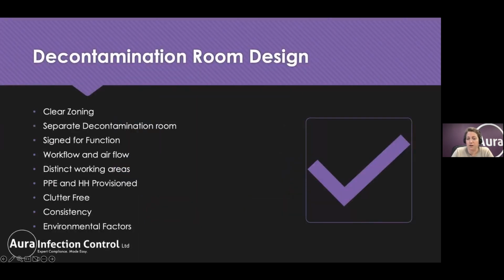And our decontamination room should be built to perform some clear functions. So the design, the suitability, and some different factors that make it fit for purpose should include things like the zoning, that we know exactly at every point in the room and every area in the room what that area is for. What are we going to be doing in that particular area? Is it a clean area or a dirty area? Your decon room should also be able to meet the workload demands. So maintaining a fresh supply of reusable items. And that might mean you have to consider including within your decon room design the use of automated processes or machines, and think about the demands that they then have on space and water and power.